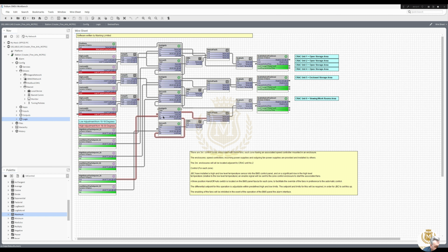So let's just prove that one working. So it's 28 and 18, zone 3. So if I override that, emergency override, and put that to 30 for example, 30 is in there, 30 is in there, oh there's a 10, it's parts per million, sorry. So 30 degrees there, into there, but I've got a big differential there of 10, I don't want that. I never copied across these.